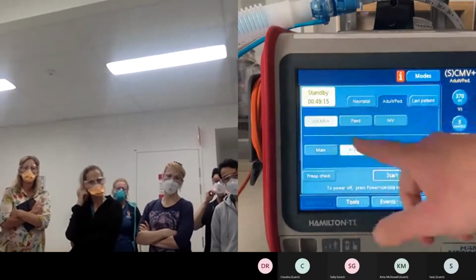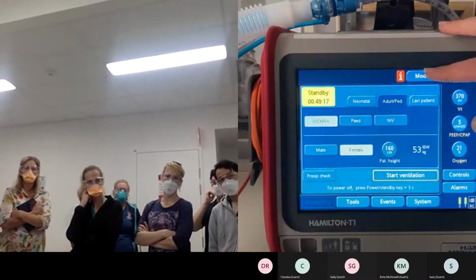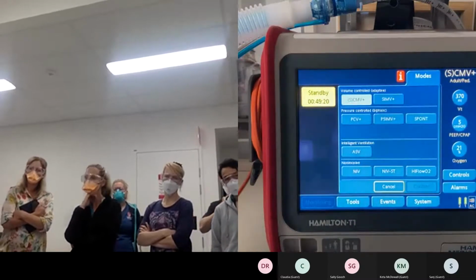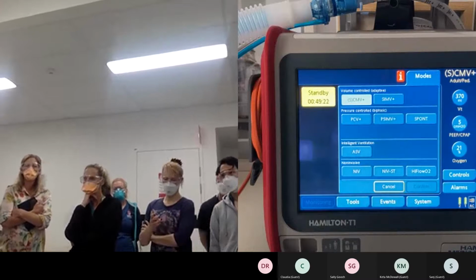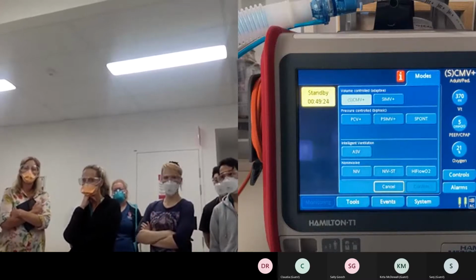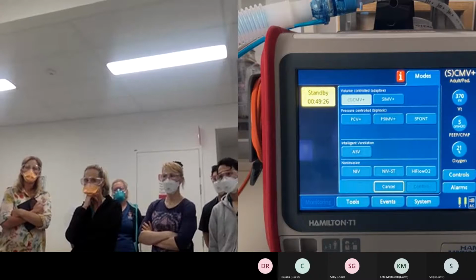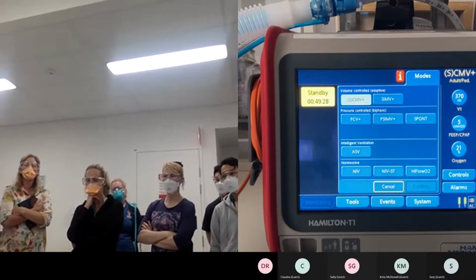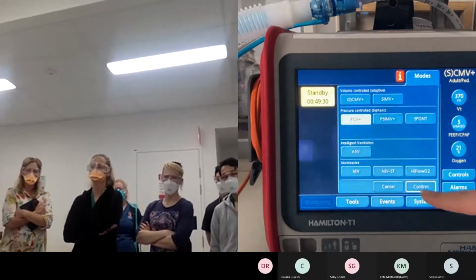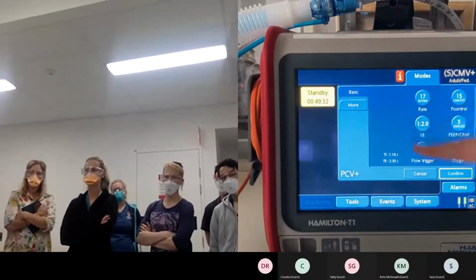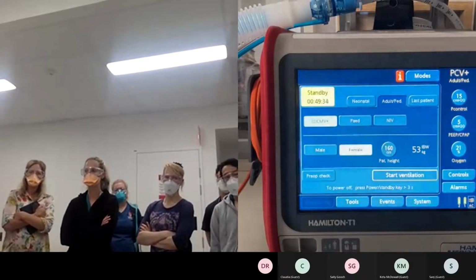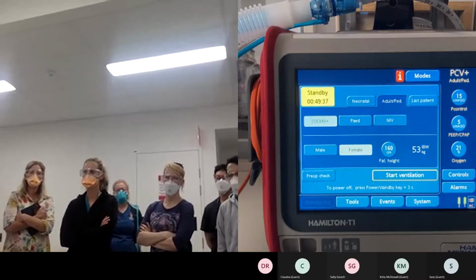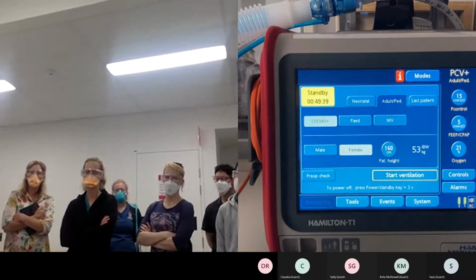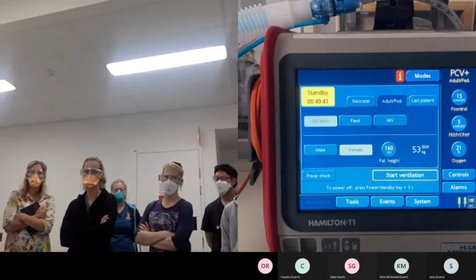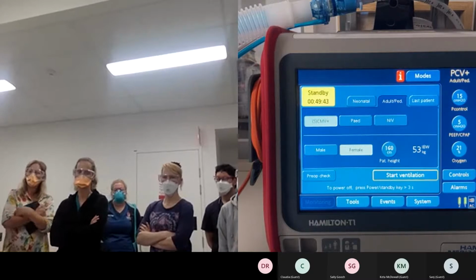Whereas if you aren't using one of those modes, see here you've got a modes tab, you touch on that and it brings up all the modes. So the modes are always there. The 3 tabs on the front are really just for your most commonly used, just to get the vent up and running quicker. Okay. So if you were using one of these, you could come in here, set it all up, and then you'd hit confirm and you'd have that mode ready to go. So whatever mode is sitting up in the right-hand corner is the mode that you're going to be active in. Okay.